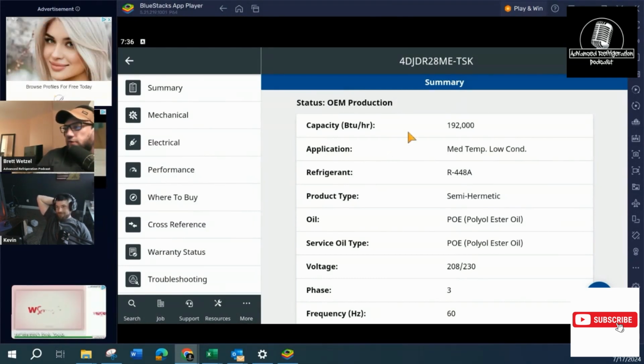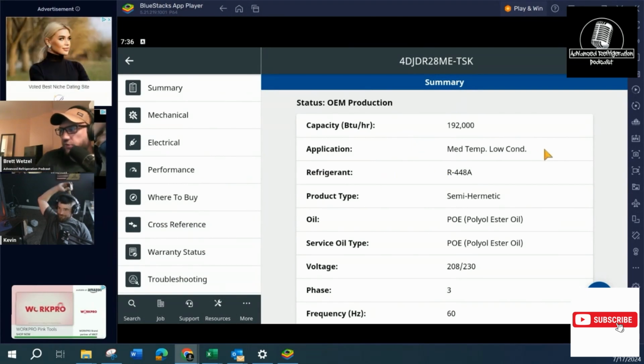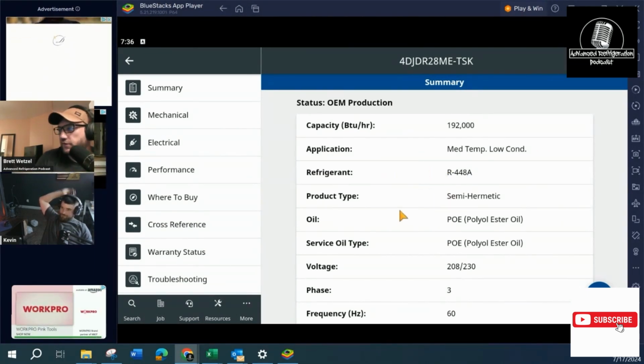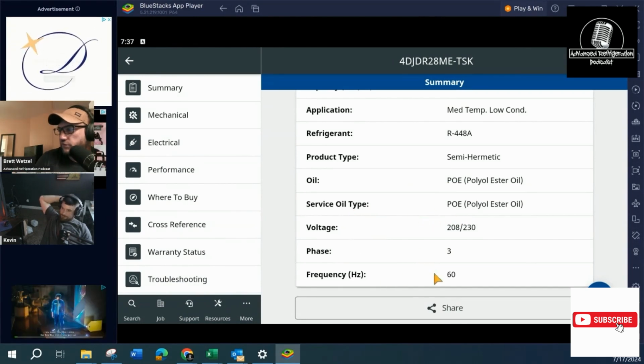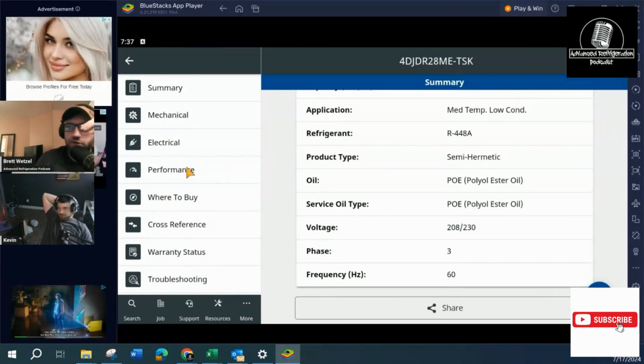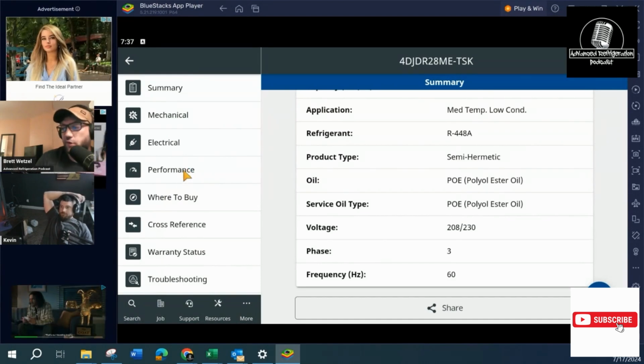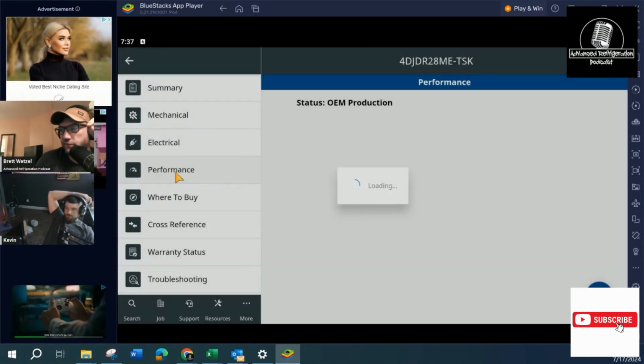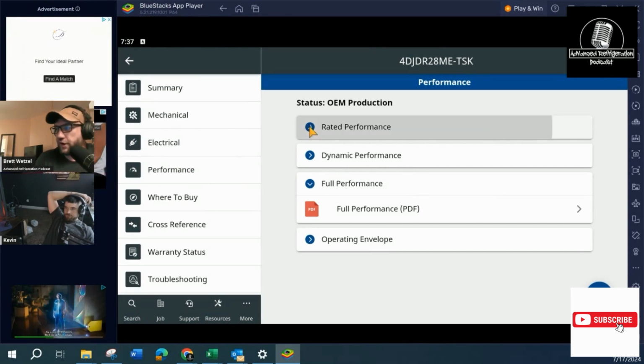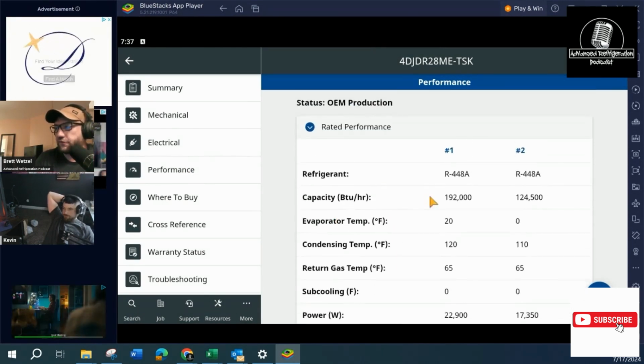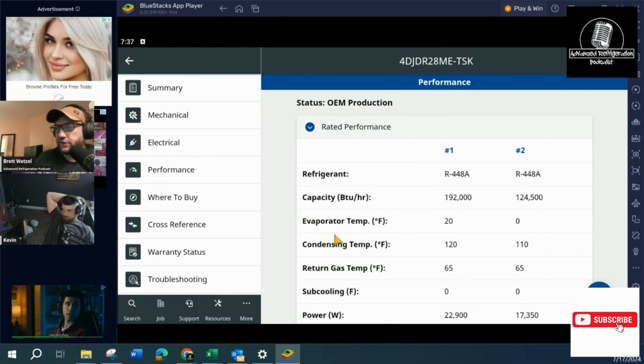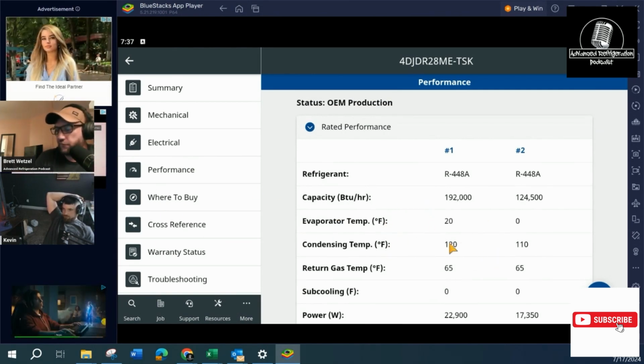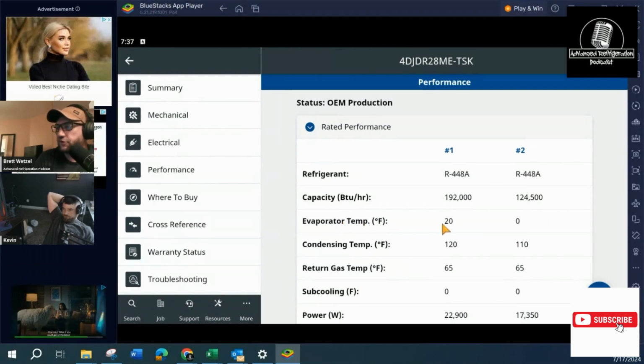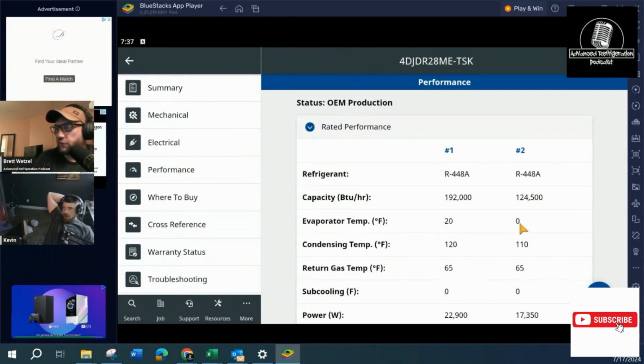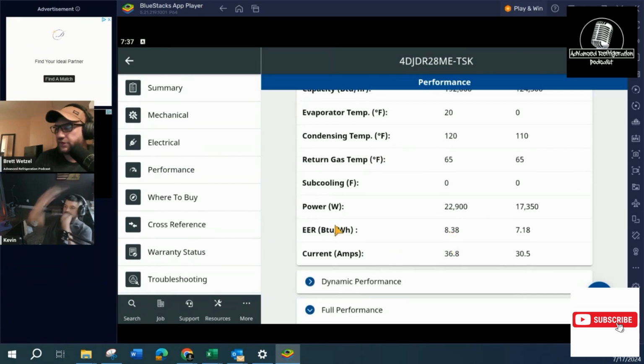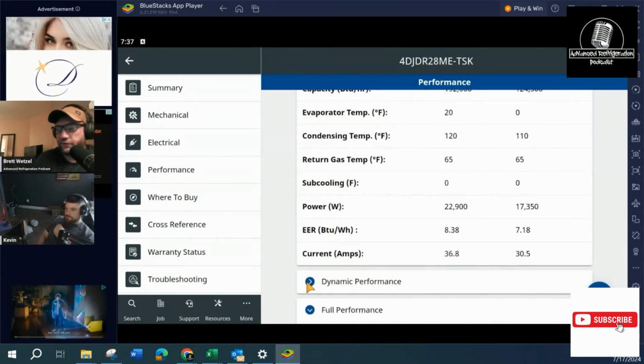All right. So when you're doing this, it'll give you the capacity of the compressor. It'll give you medium temp, low condensing, 448, the refrigerant, semi-hermetic, what oil you have in there, voltage, phase, and the hertz. If you want to figure out the performance, first you have to go to regular performance. Then if you go to rated performance, it'll give you the staples of what it will run, which unfortunately doesn't let you move these numbers about. So you have evaporator temperature. What if you would run it at 20? What if you would run it at 0? And so on and so forth. That's lame because it's not really going to help us if we're trying to diagnose something.